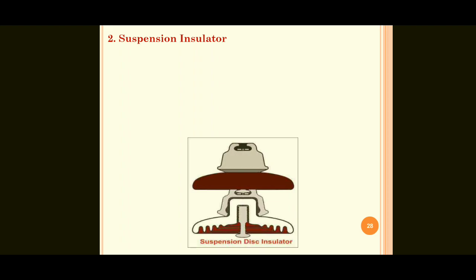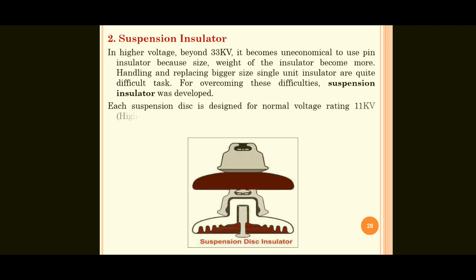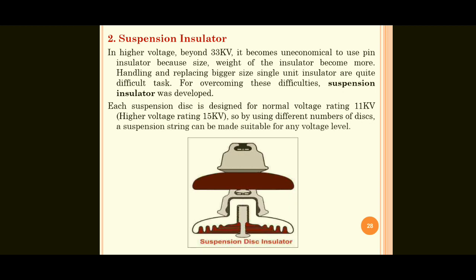Next one, suspension insulator. Now this figure shows the suspension type disc insulator. At higher voltage, beyond 33 kilovolt, it becomes uneconomical to use pin insulator because the size and weight of the insulator become more. Handling and replacing a bigger size single unit insulator are quite difficult tasks. To overcome these difficulties, the suspension insulator was developed. Here the first point is that pin insulators and suspension insulators are used in high voltage ratings. Pin insulator is used only for 33 kV.